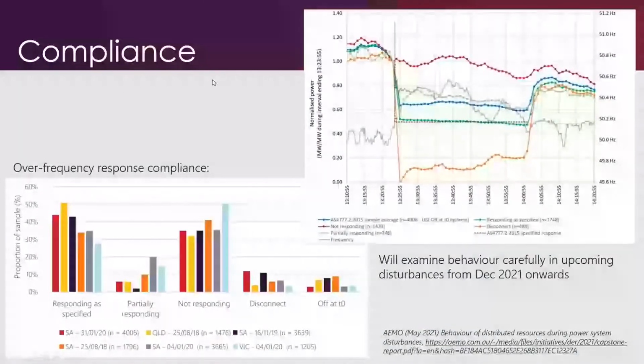But just a note on compliance. I mentioned that we've seen evidence of inverters not complying in the field. This is just some of the evidence we've collected around that. This chart up the top here shows the responses of PV inverters that we recorded based on the data sets from Solar Analytics, where they're recording systems less than 100 kilowatts, thousands of them across the NEM. This was looking at a particular event where we saw an overfrequency. You can see here in the grey the overfrequency event that occurred.